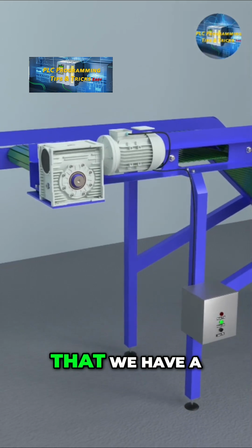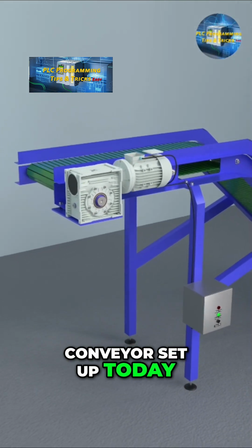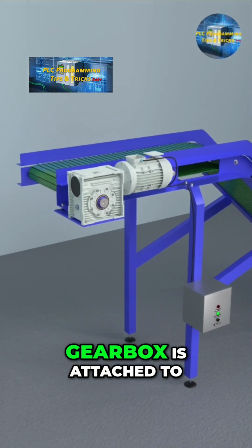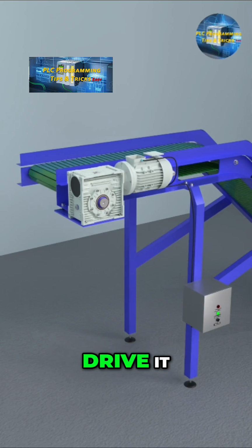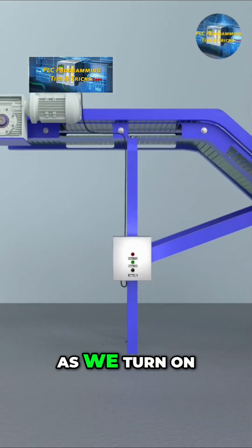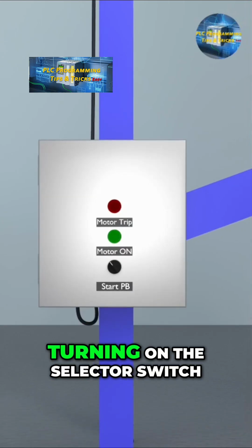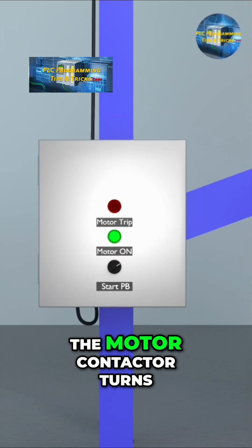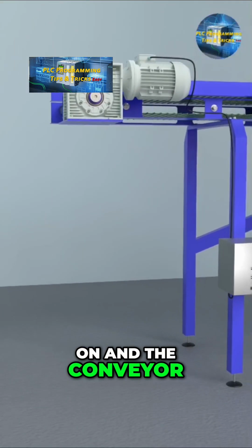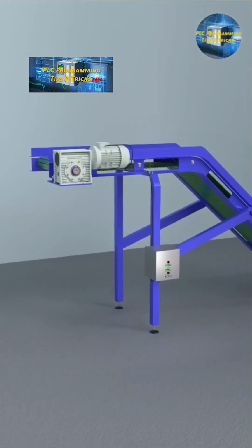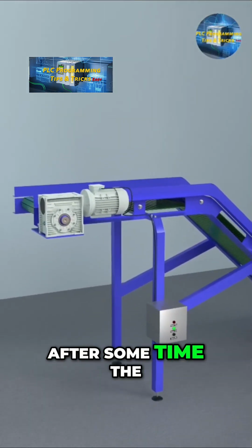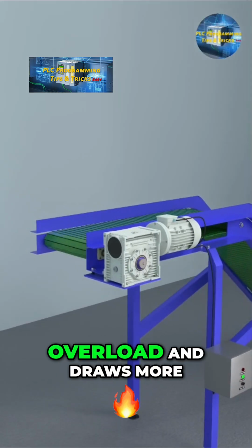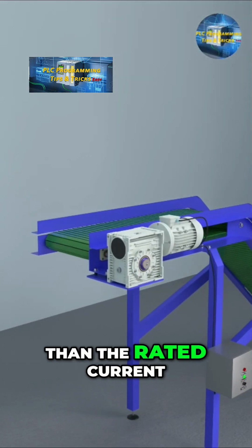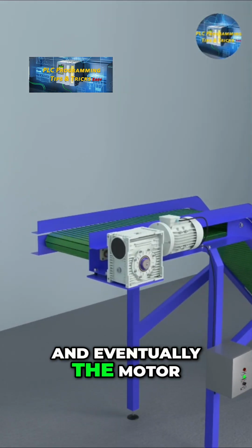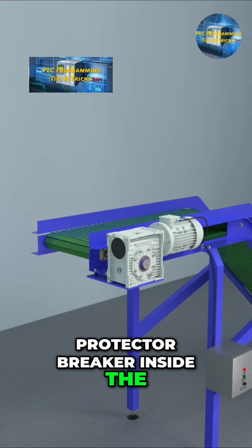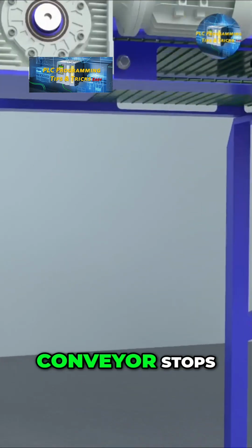As you can see, we have a conveyor setup today. A motor and a gearbox are attached to the conveyor chain to drive it. As we turn on the conveyor motor by turning on the selector switch, the motor contactor turns on and the conveyor belt starts to run. After some time, the conveyor motor starts to overload and draws more than the rated current, and eventually the motor protector breaker inside the control panel trips and the conveyor stops.